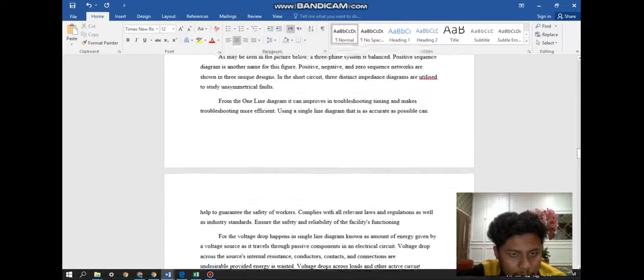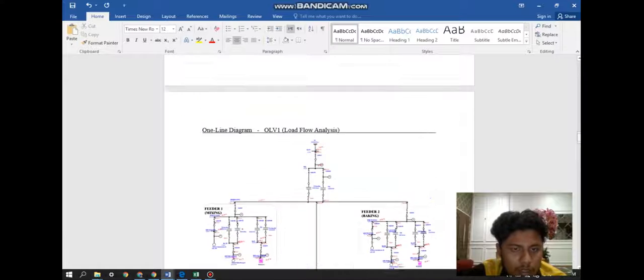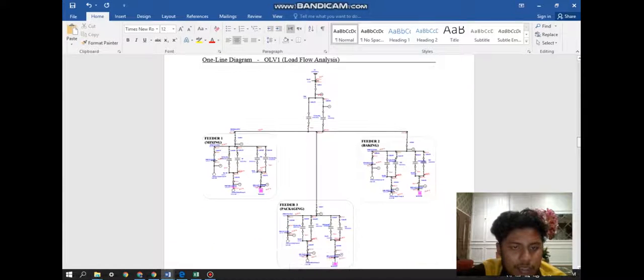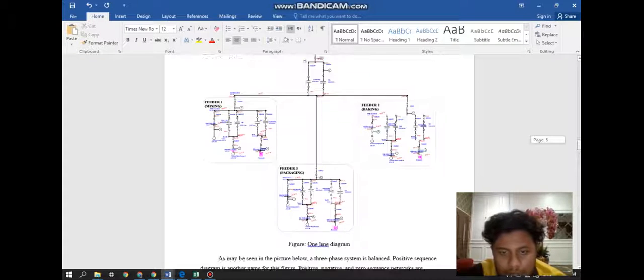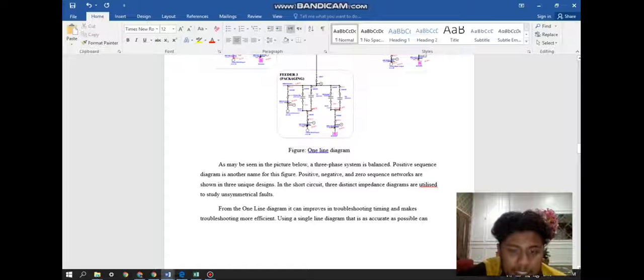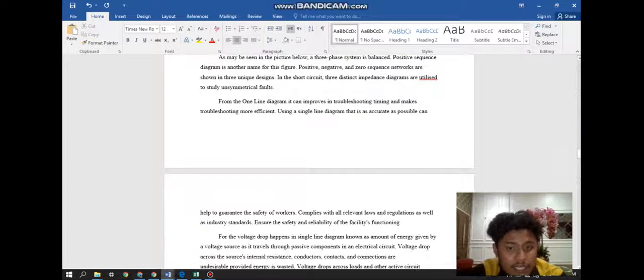Okay, so I proceed with 3.2 right here. So this is 3.2, the outcomes of industrial network design. So this is a one line diagram. As may be seen in the picture right here, a three-phase system is balanced, so positive sequence diagram is another name for this figure. Positive, negative and zero sequence networks are shown in the design. In the short circuit study, three distinct impedance diagrams are utilized to study asymmetrical faults. So the one line diagram can improve troubleshooting timing and makes troubleshooting more efficient. Using a single line diagram that is as accurate as possible can help to guarantee the safety of the facility and compliance with all relevant laws and regulations as well as industry standards.